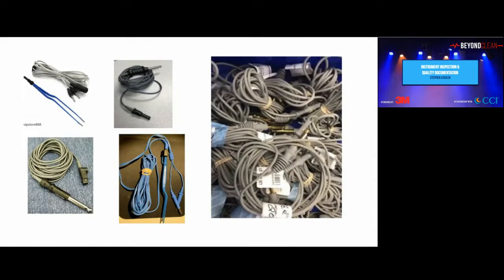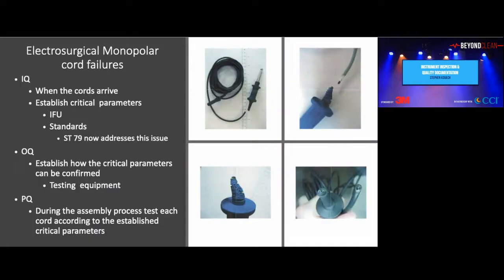So here's the cord. These are cords that were shared with me, pictures that actually burned and caused problems. Look at those. Inspect when the cord arrives, establish the critical parameters - the IFU standard 79 addresses this issue. You should check it when it comes in: no nicks, it's all intact. You pull it, make sure it doesn't come apart. Do both the cord and inside the wire.